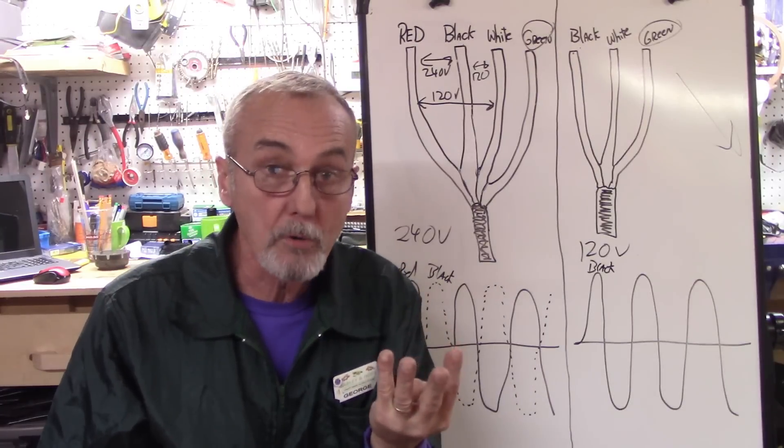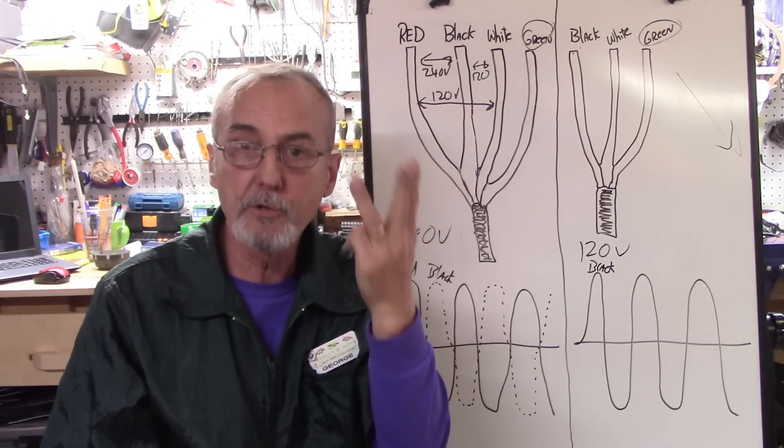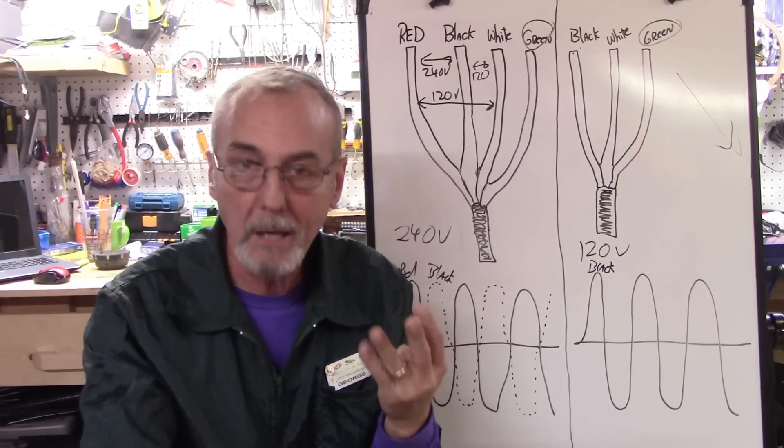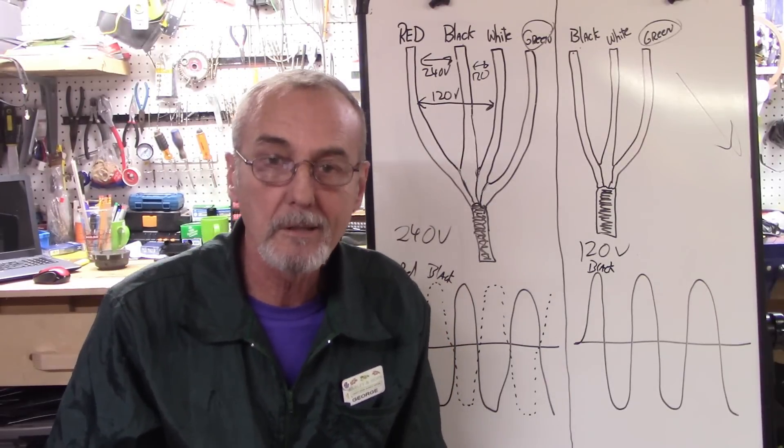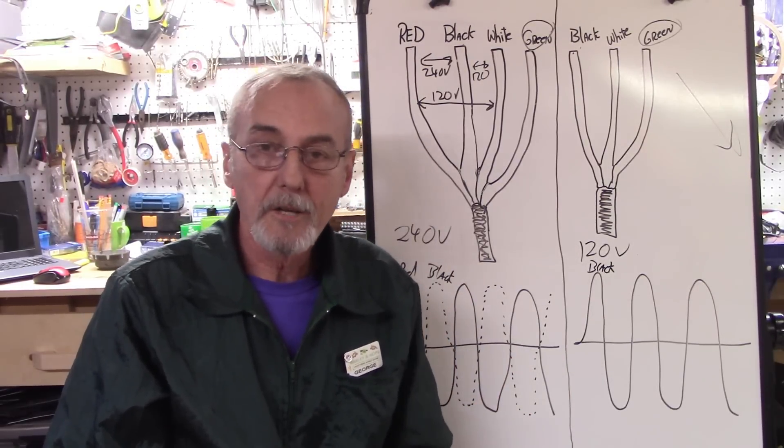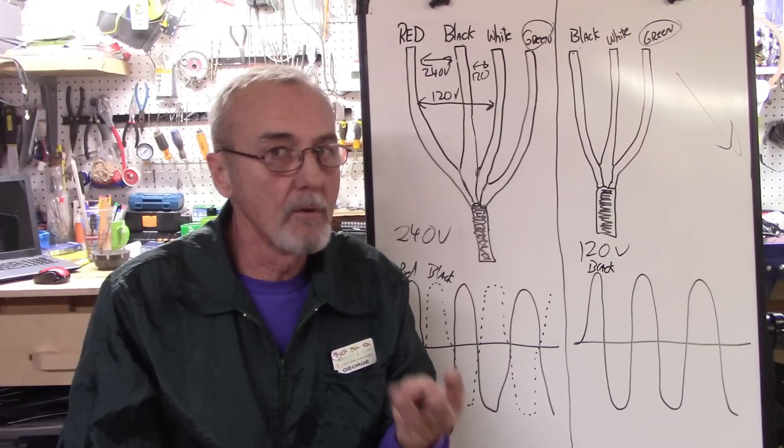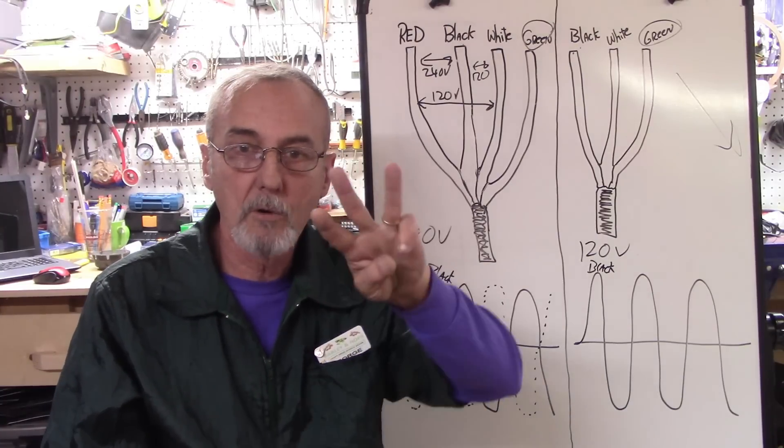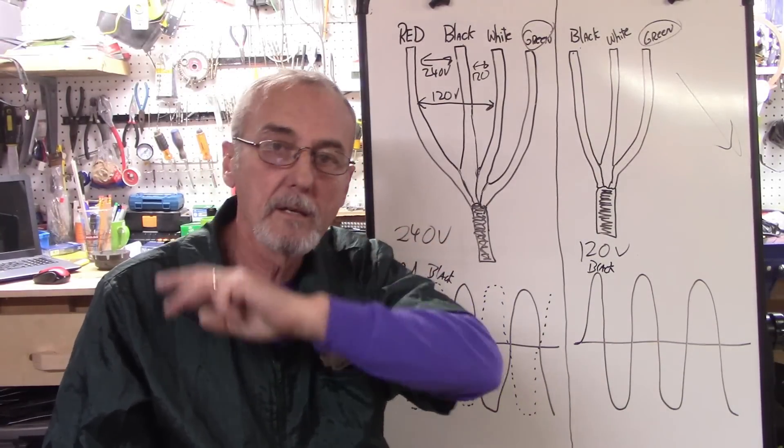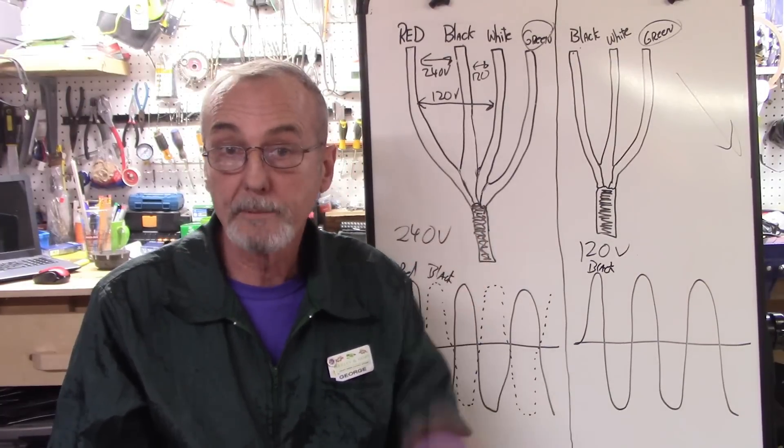You've got a four-prong dryer. That's a hot, a hot, a neutral, and a ground. It's probably because the buzzer works off of 120 volts. You'll have other appliances that will have only a hot, a hot, and a ground. And so that's a 240-volt three-prong or three-wire.